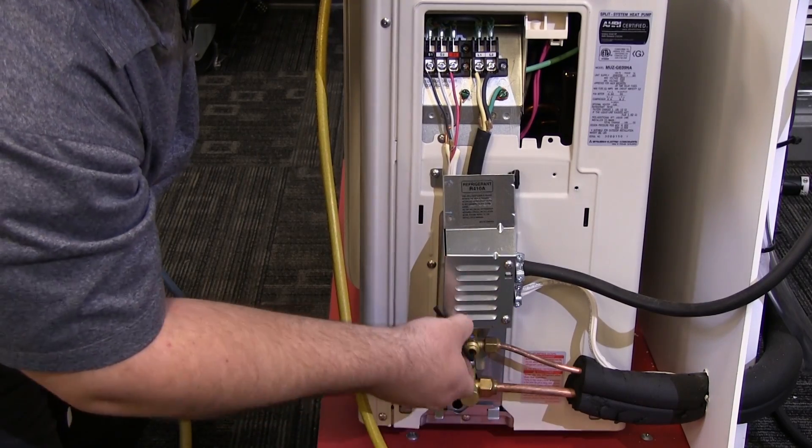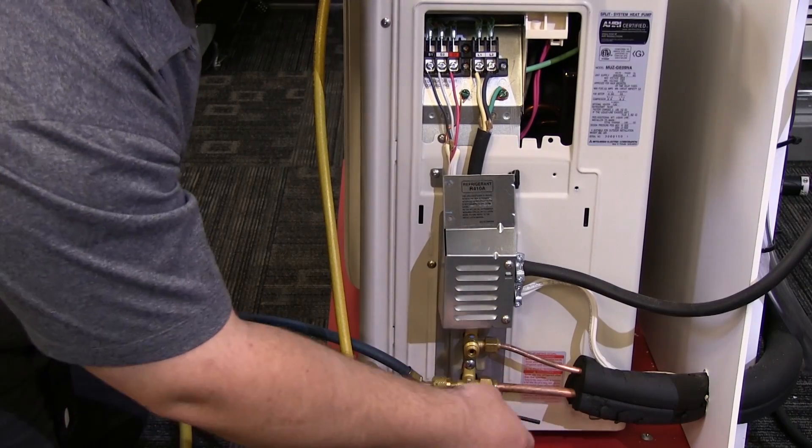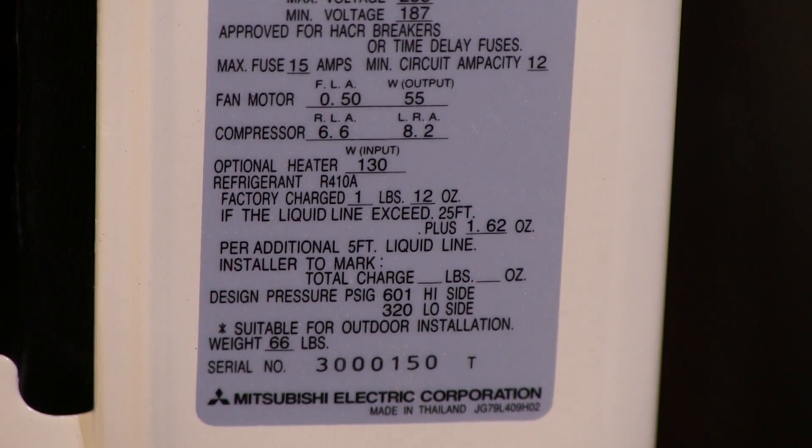Now we can open the service valves. Since our line set is under 25 feet, there is no need to add any additional charge. The name plate of the outdoor unit will always advise you if any additional charge is needed, depending on the line set length.